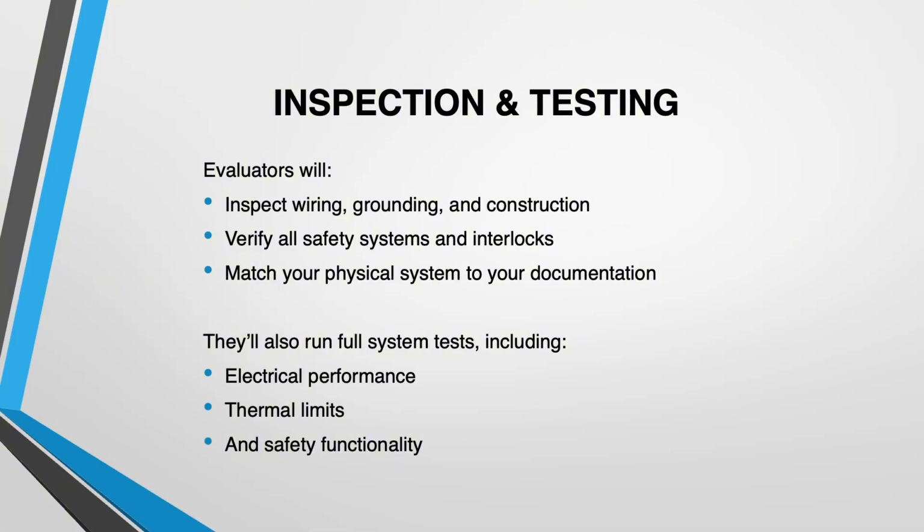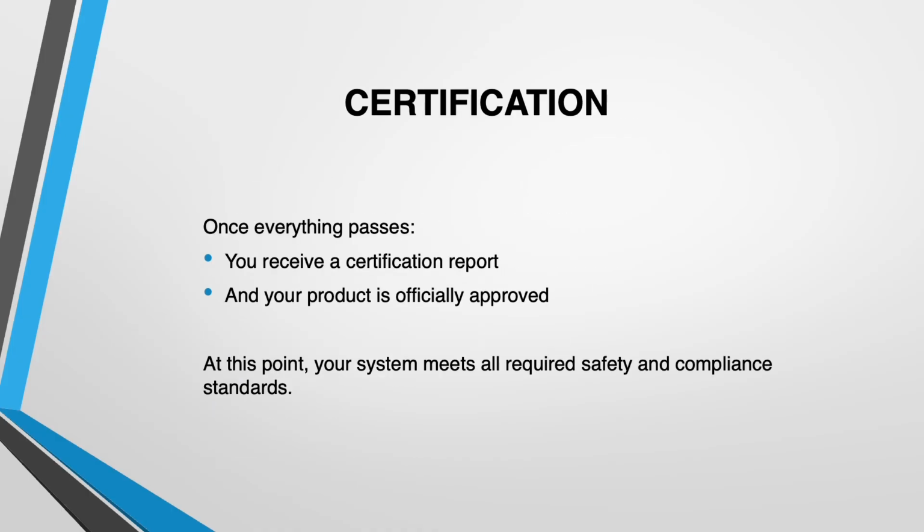Evaluators will inspect wiring, grounding, and construction, verify all safety systems and interlocks, and match your physical system to your documentation. They'll also run full system tests, including electrical performance, thermal limits, and safety functionality. Once everything passes, you receive a certification report, and your product is officially approved.